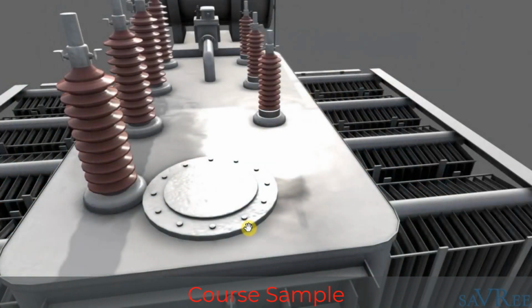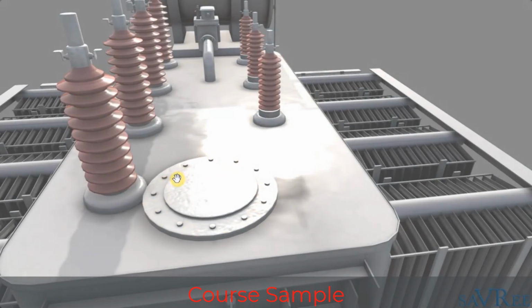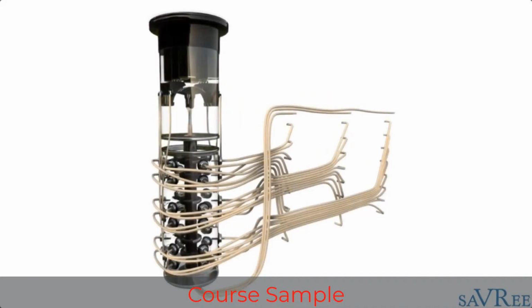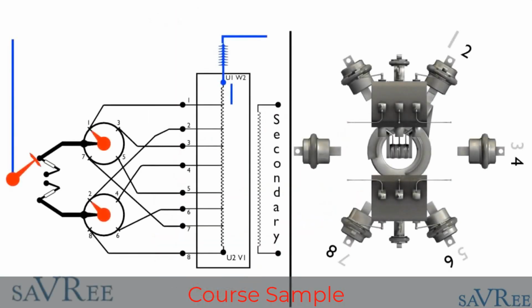The load tap changer is mounted in this section, and this type of tap changer is mounted directly within the transformer tank. That's not always the case. Sometimes the tap changer will be mounted externally, or perhaps it will have its own compartment within the transformer tank. The disadvantage to having a tap changer directly within the tank is simply that it shares the same insulating liquid as the transformer.